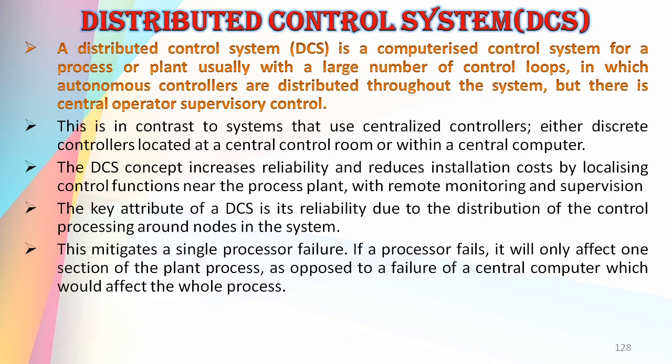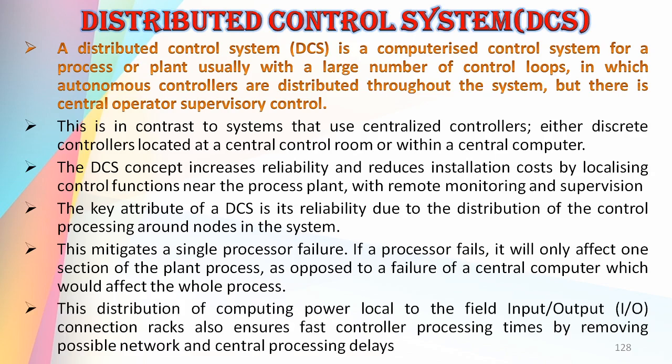That is the main advantage and main difference when compared to a SCADA system. This distribution of computing power local to the field input or output connection racks also ensures faster controller processing time by removing possible network and central processing delays.